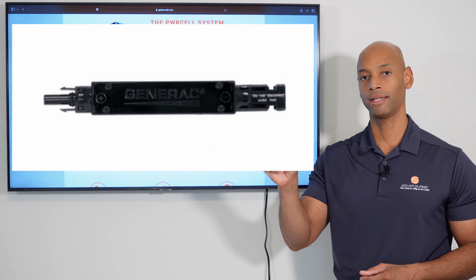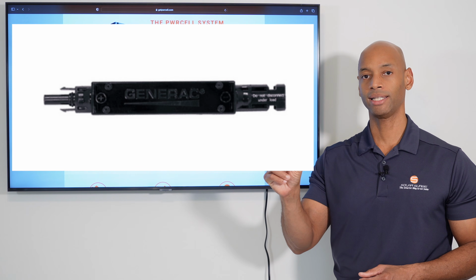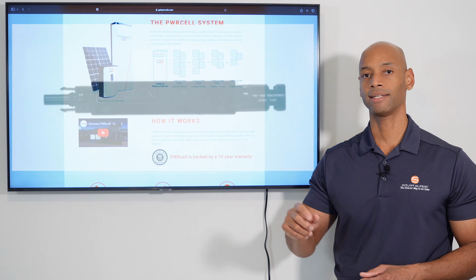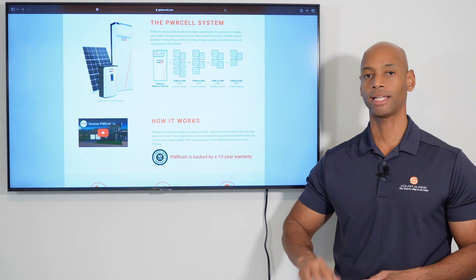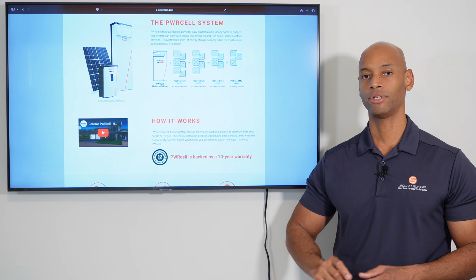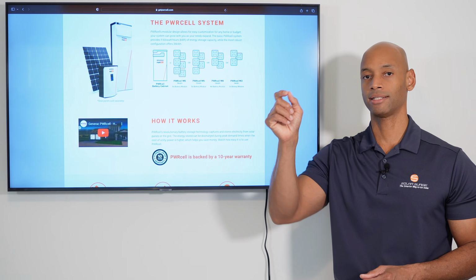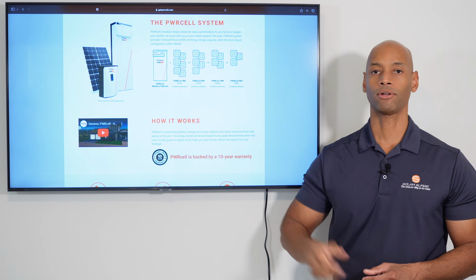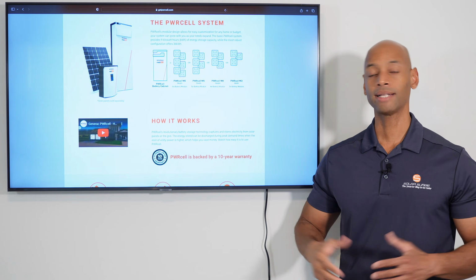This was basically a remotely controlled relay that could be disconnected. If it received a signal from ground level that the grid connection was down, it would send a signal up to the Snap RS, and the Snap RS would disconnect the solar panel circuit. So that's how it's supposed to work.